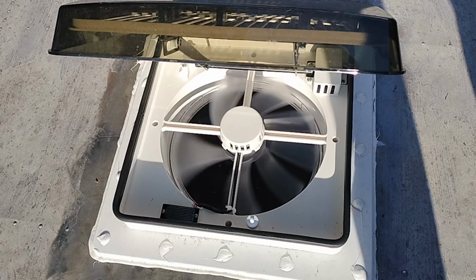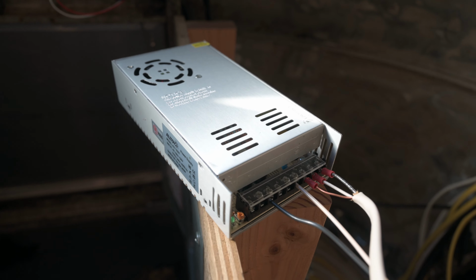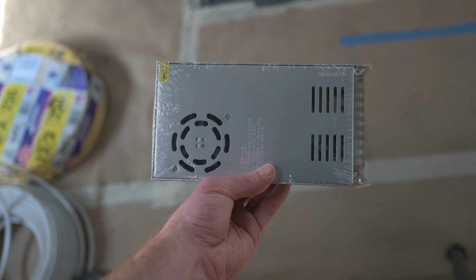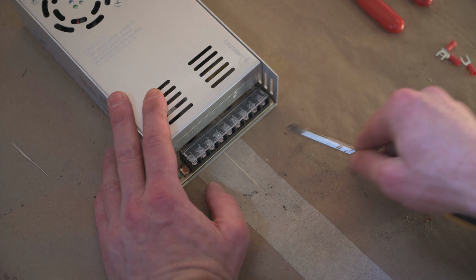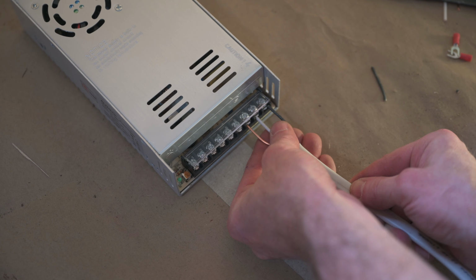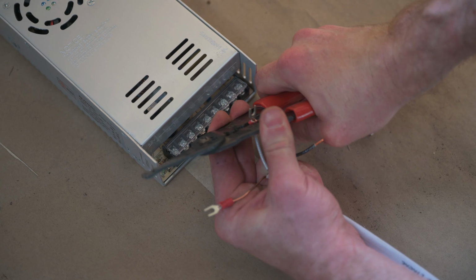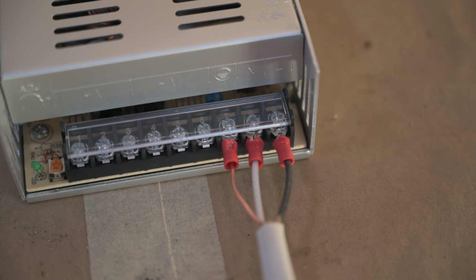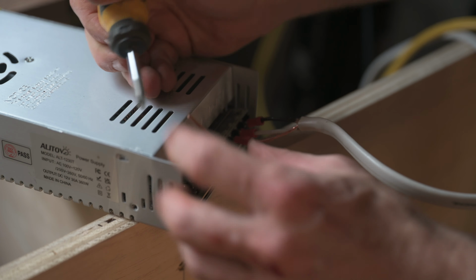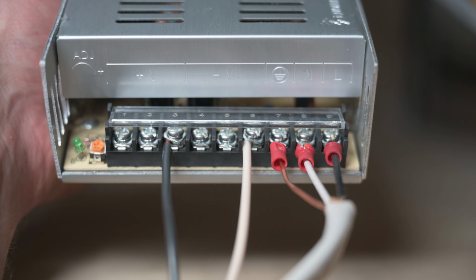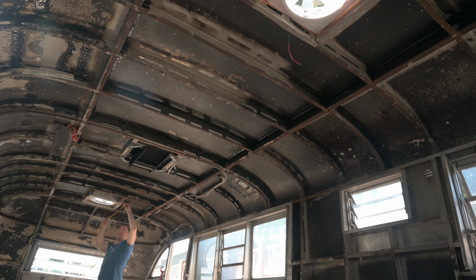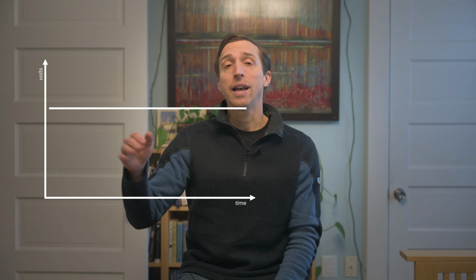The roof vents run on 12 volts DC, so we bought this 360 watt DC power supply. We ran a 14 gauge cable to supply it with AC power and put these forked crimp connectors on the end to screw into the terminal strip. Black to line or hot, white to neutral, and bare to the ground symbol. Then we connect a 12 gauge cable to the positive and negative sections of the terminal strip and route it to the fan. In case you're not familiar, DC stands for direct current, and it's a steady voltage, just like what you get out of a battery.